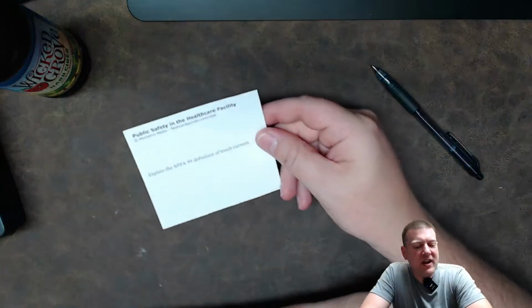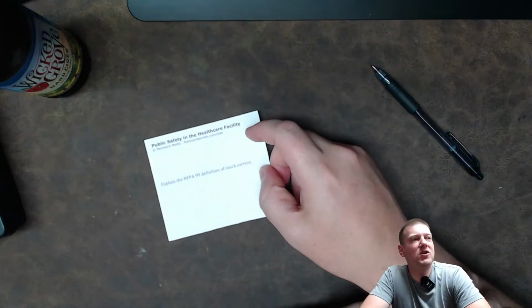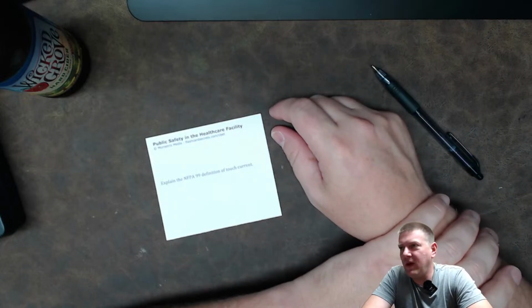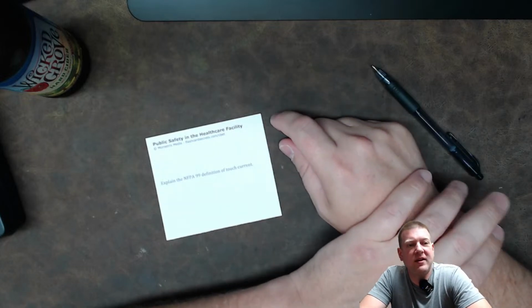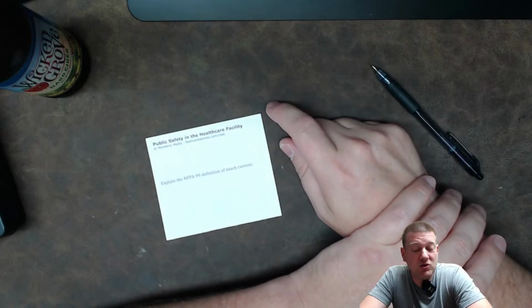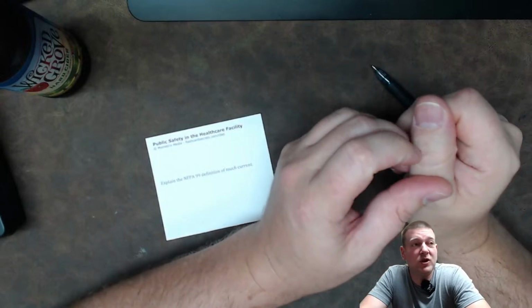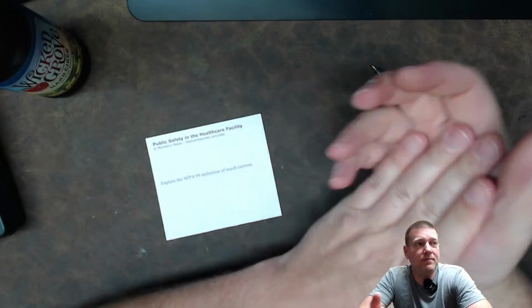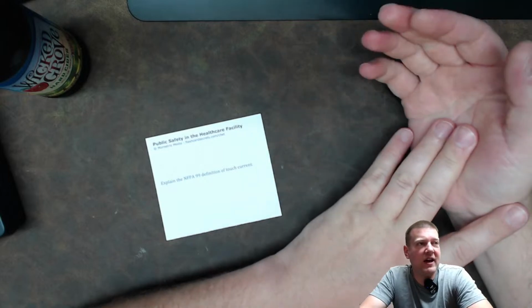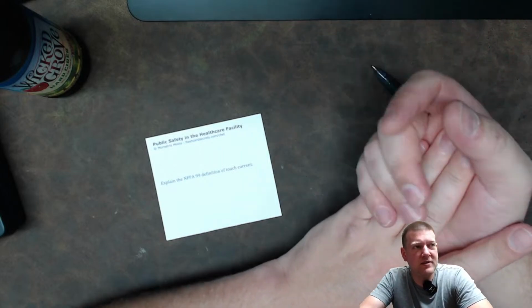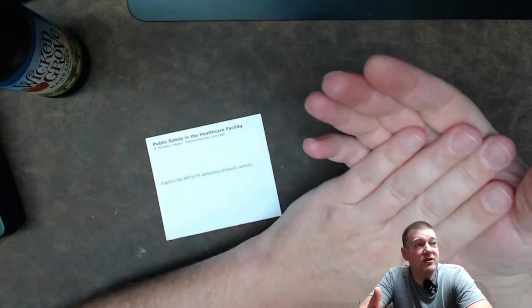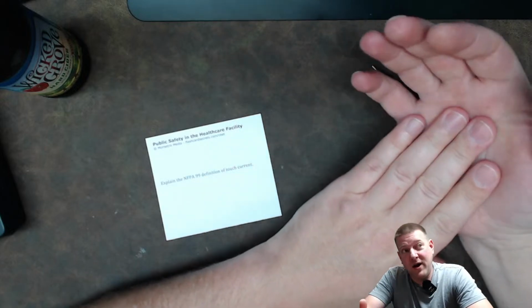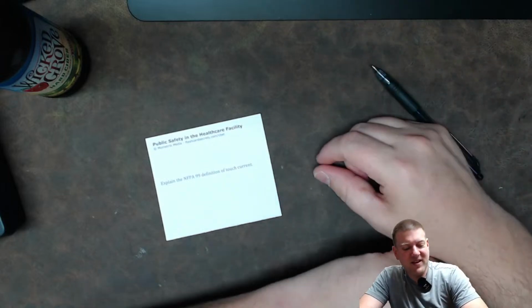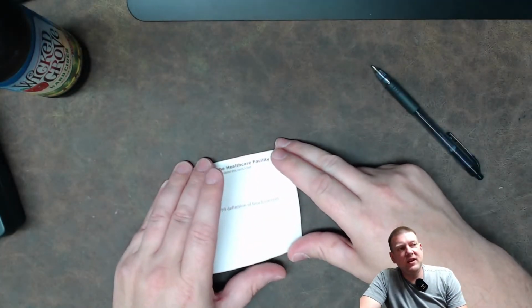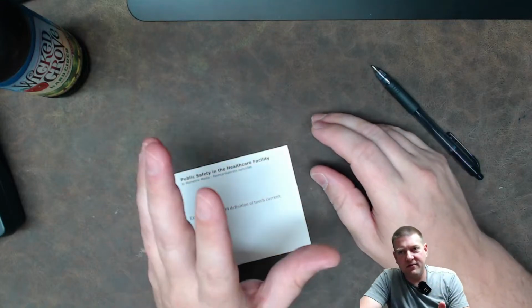Next, explain the NFPA 99 definition of touch current. This is the type of question I'd expect on an exam. You should know this, and the limits as well. You do electrical safeties every day, so you should know the current limits for chassis leakage or touch current leakage or ground leakage. So touch current is the amount of leakage between the chassis of a device and somebody that touches it.